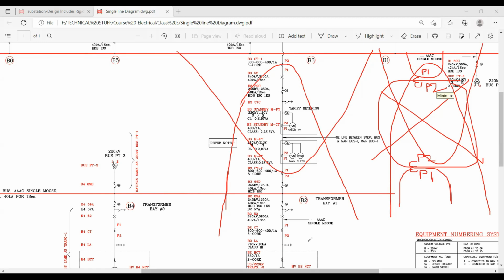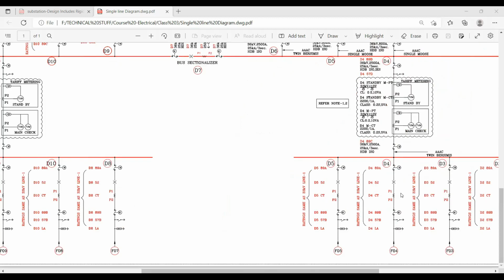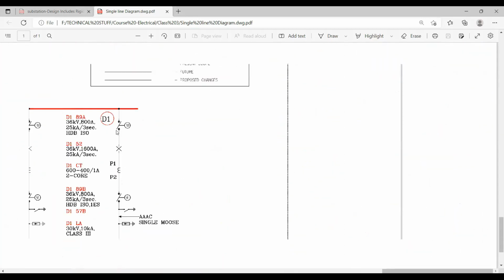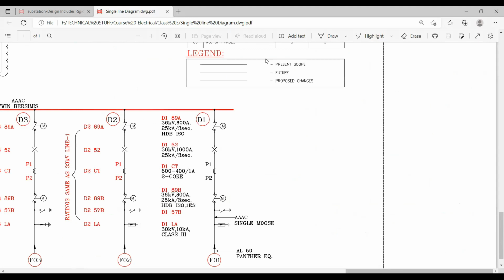89B, 57B, confusing, like D1 89B. Yes, let's come down. Why confusing? Let's see. I have two isolators. To differentiate them, generally this is D1 89, this is also D1 89, and this is D1 57. To differentiate, I take this one as 89A and this as 89B. This earth switch is associated with this isolator, meaning it depends upon this isolator. When this isolator is opened, this should be closed. When it is closed, this should be open. So for this, I give the same designation, 57B, to this. Clear now? You can have A this, B this, or B this, A this, whatever.